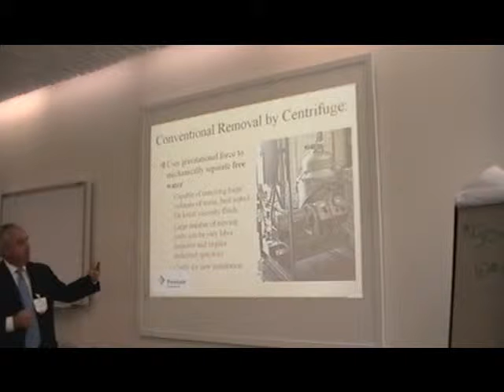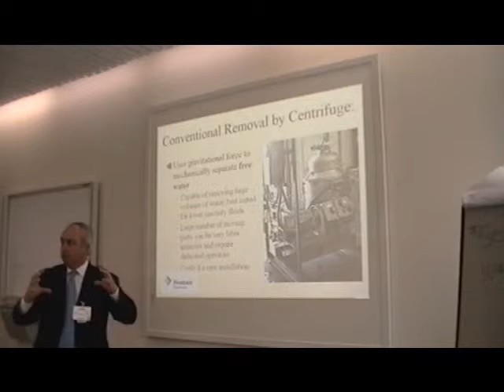Centrifuges are capable of removing moisture or a lot of gross water. If you had hundreds of gallons of water in the system, you might be able to get to it with these. The difficulty is they're not going to touch an emulsion, and obviously they're not going to do anything for dissolved water.